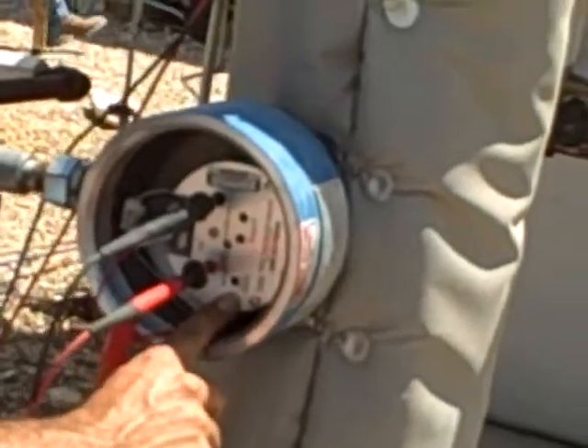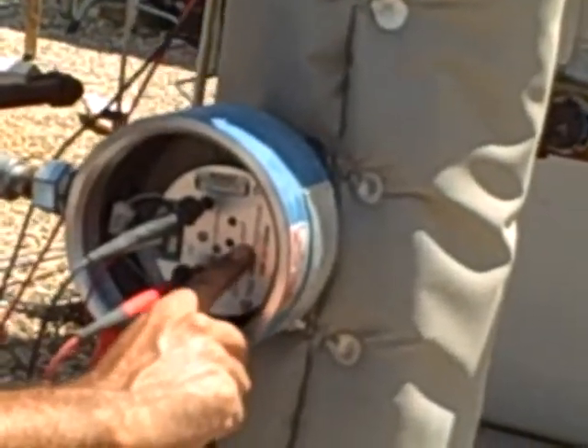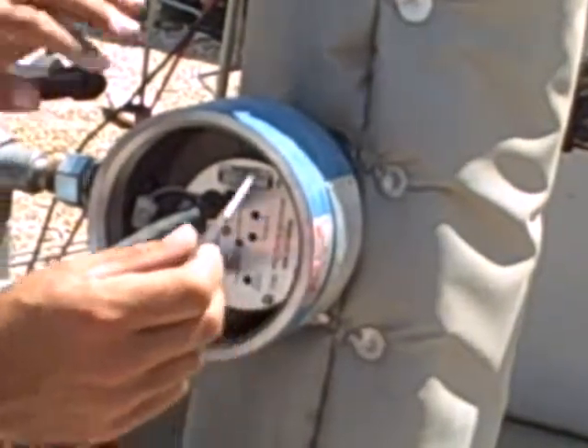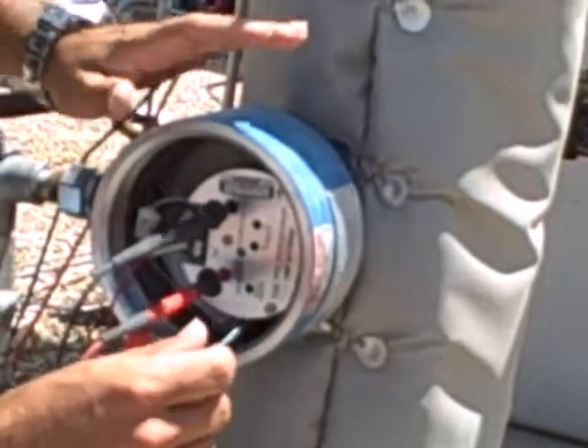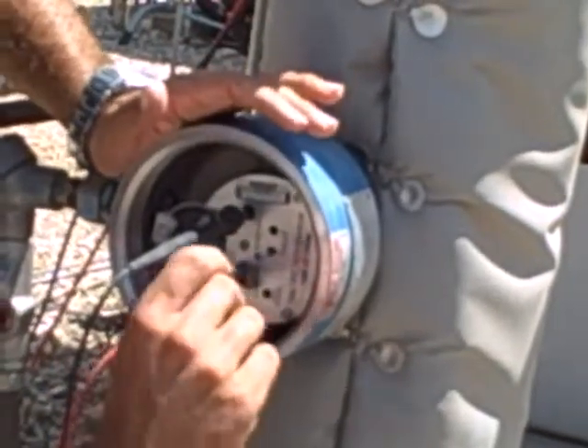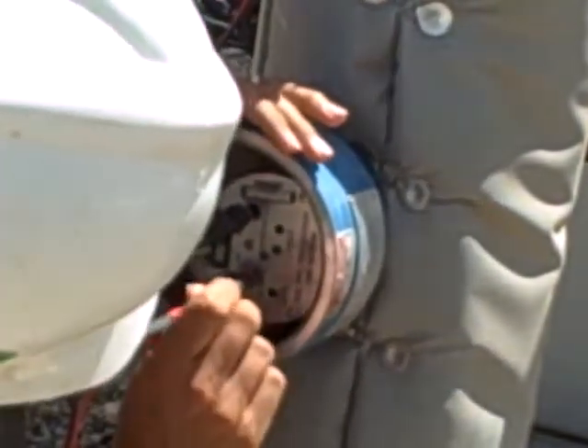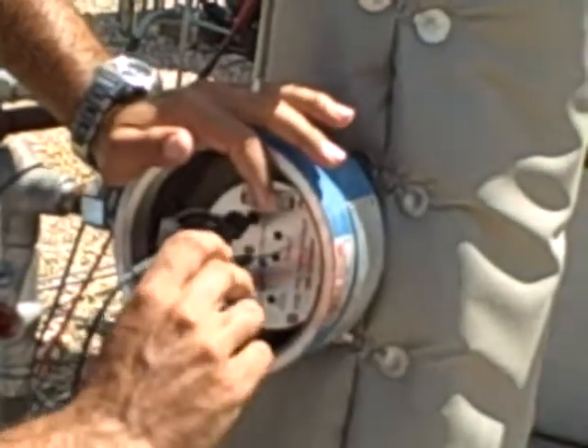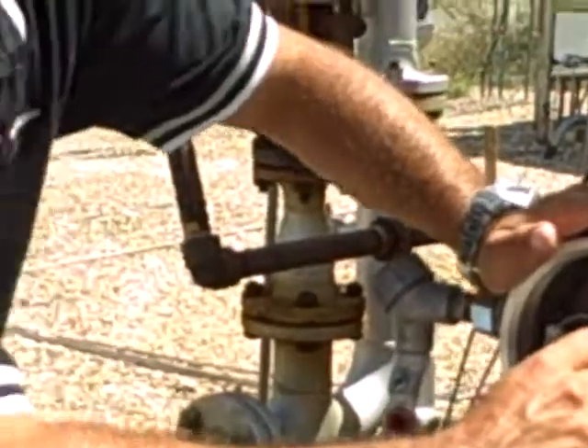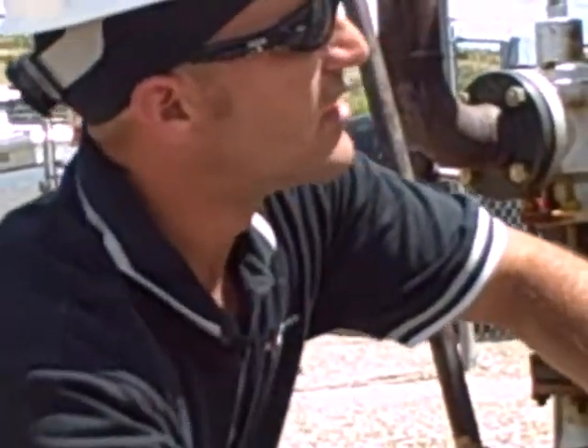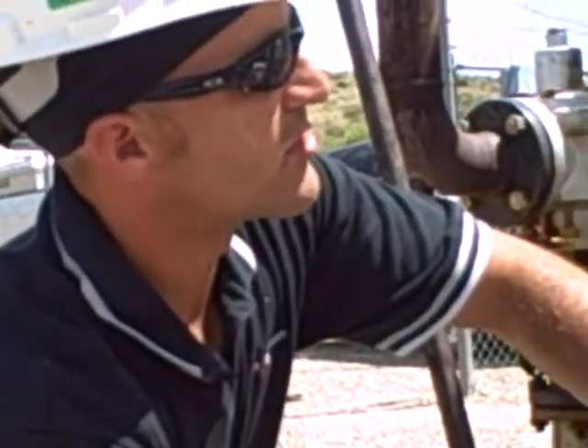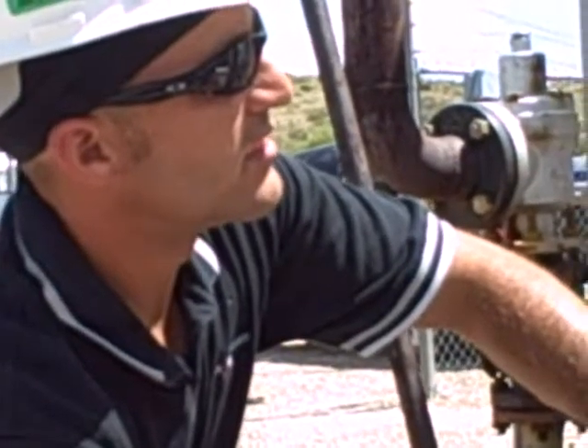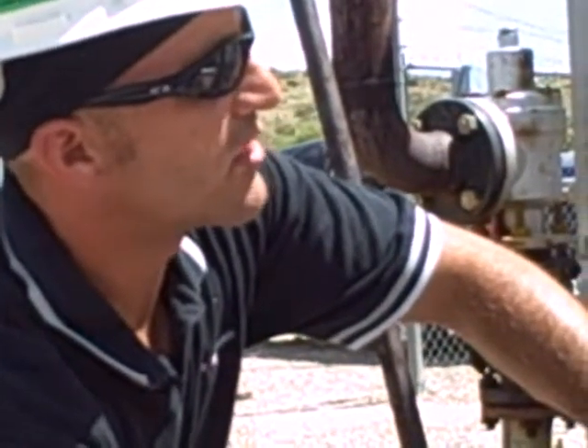Here you have the 0 and the output span. What we're going to concentrate on here is the 0. I need to make sure my toggle switch is on the probe. Since we're doing the lower portion, like I said, we're going to go ahead and do 0. I always use the C, which will be your coarse measurements. You can use the F, which is for fine measurements, but you can really get it with this C a lot easier. So you go ahead and start to turn it slowly. Alright, I'm going the wrong way, so I need to turn it the other way.